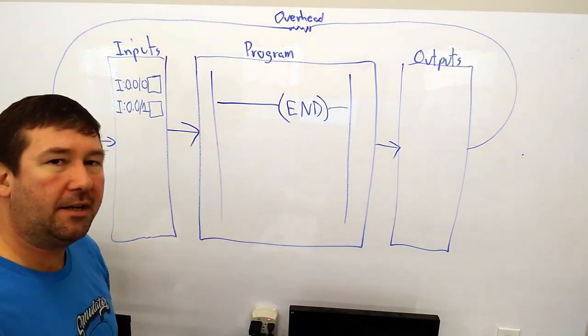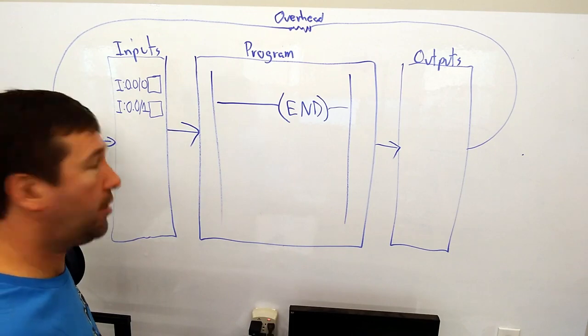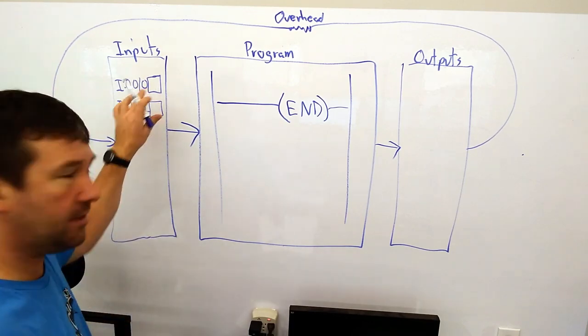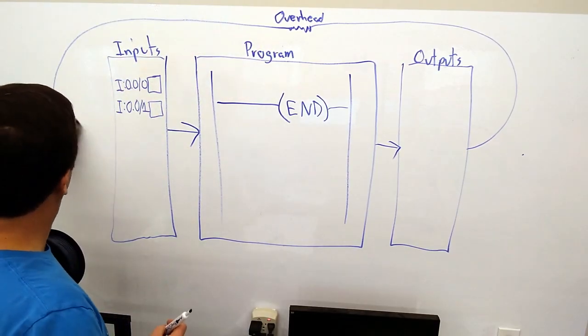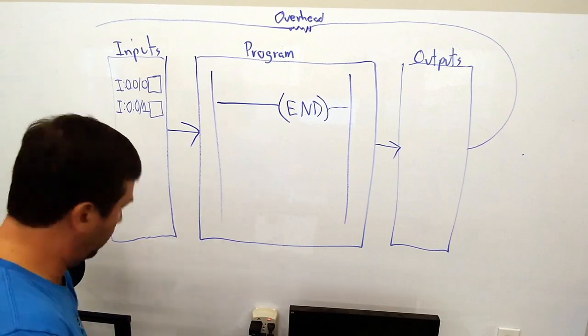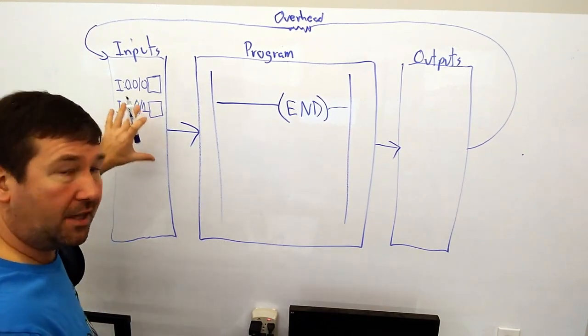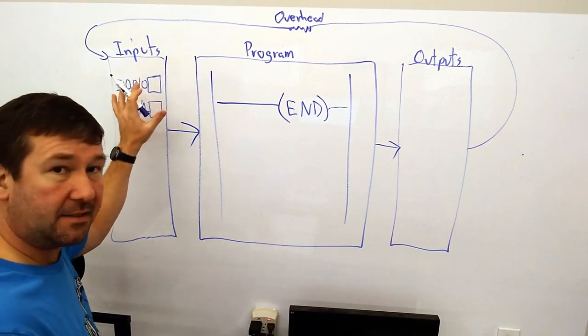But when you read an input in a program, are you actually reading the physical input, or are you reading these boxes? The answer is you're actually reading these boxes. And at this first step right here, I'm actually going to move this up to give us a little more room. At this first input step, it actually looks at all of its physical inputs and updates these boxes.